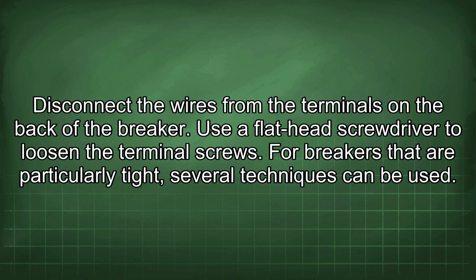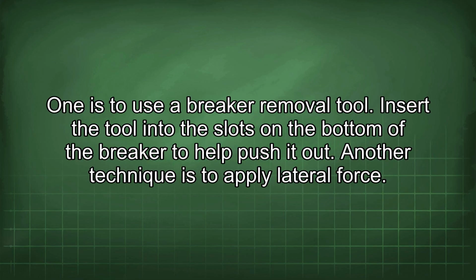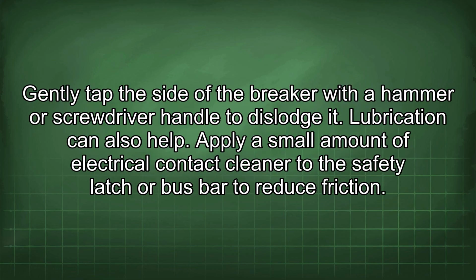For breakers that are particularly tight, several techniques can be used. One is to use a breaker removal tool. Insert the tool into the slots on the bottom of the breaker to help push it out. Another technique is to apply lateral force. Gently tap the side of the breaker with a hammer or screwdriver handle to dislodge it.